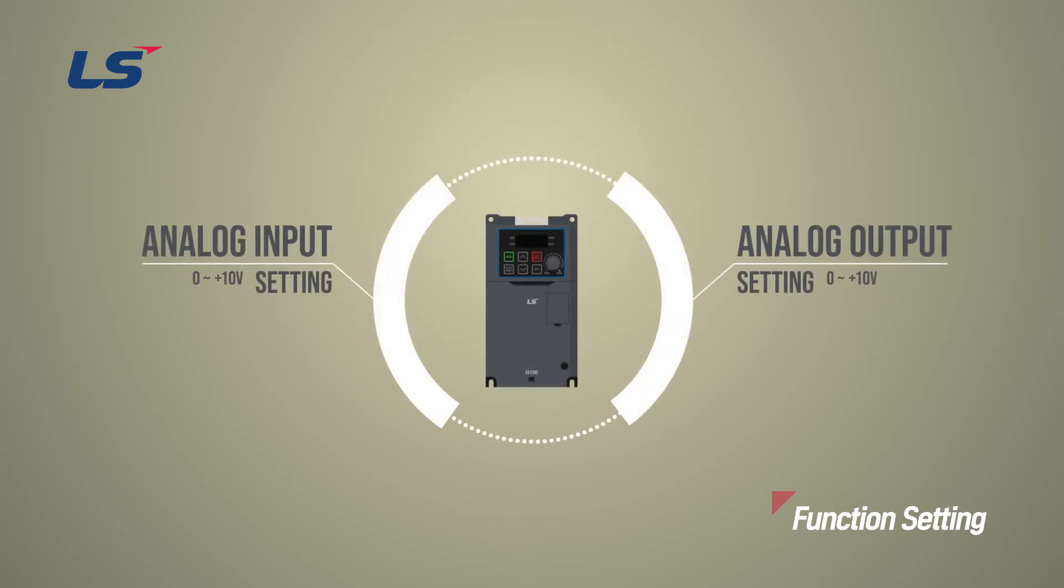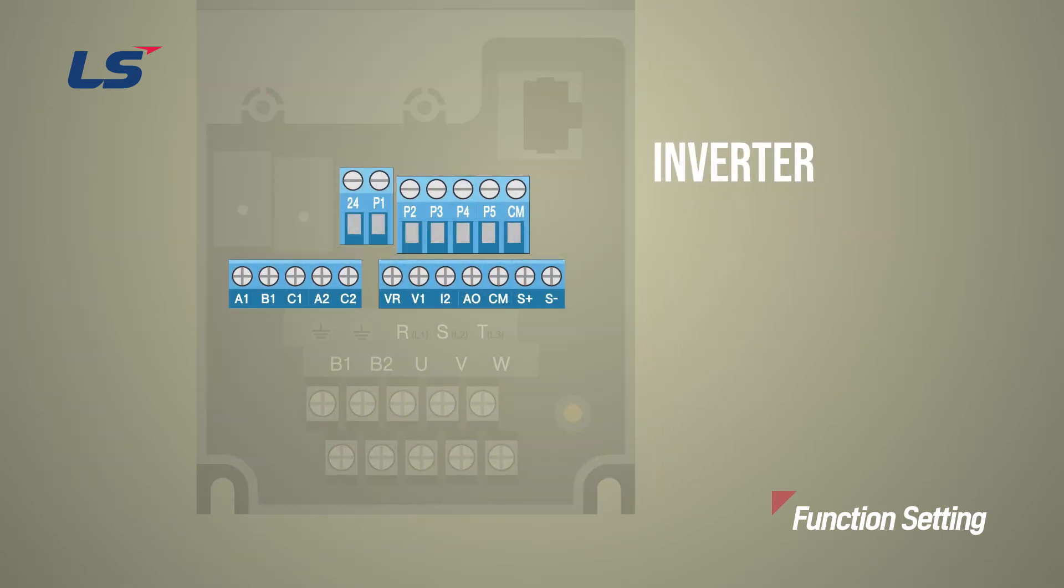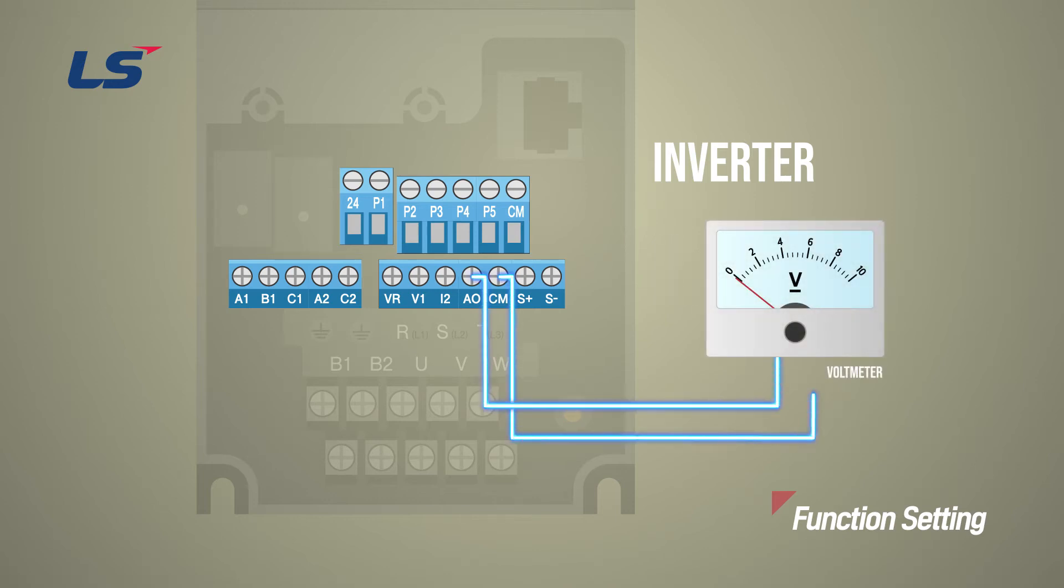Next, we will learn about setting up 0 to 10 volt analog outputs. Analog output terminals are AO and CM terminals. AO is the analog voltage output terminal, and CM is the analog input and output common terminal. To output voltage with a voltmeter, connect the two terminals AO and CM.